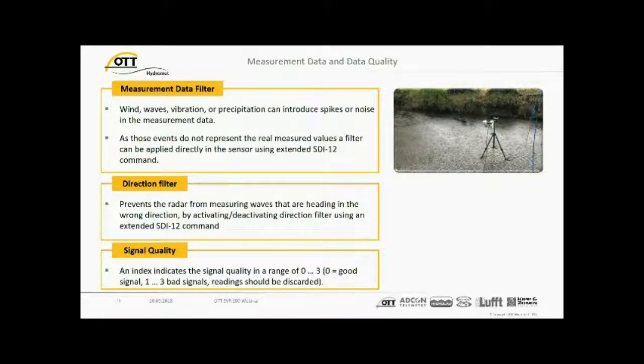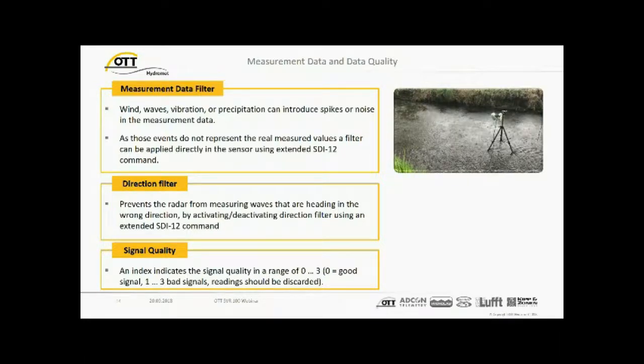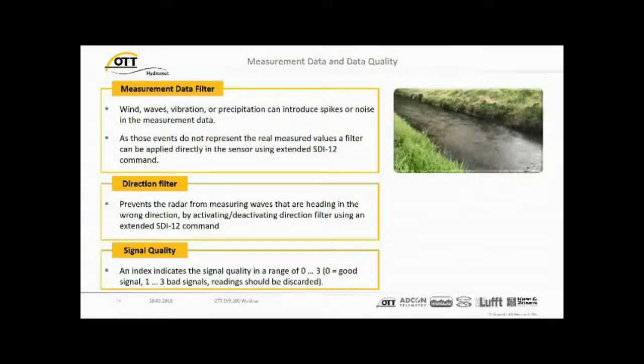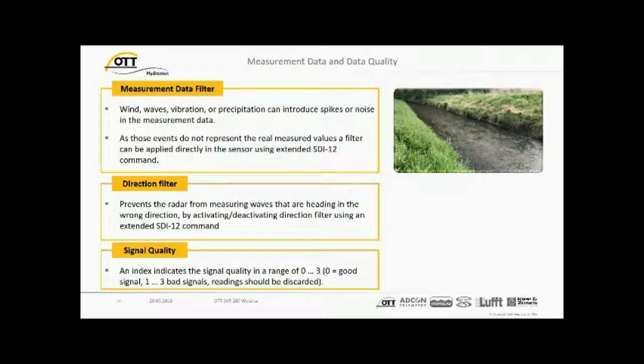We have measurement data filter algorithms. Wind, waves, vibration, precipitation can introduce spikes or noise in the measurement data. If those events do not represent the real measured velocities, a filter can be applied directly in the sensor using an SDI command. The filter length can be defined by you. As you see here in the small movie, it was a day with very heavy rainfall in the surroundings of Berlin. We were measuring, the tripod was holding the sensor. It was just a test in the field, and it worked perfectly.